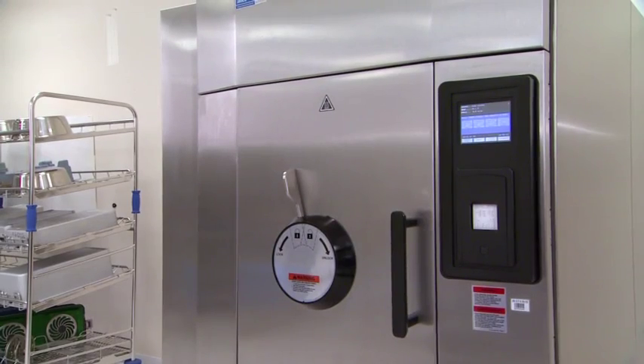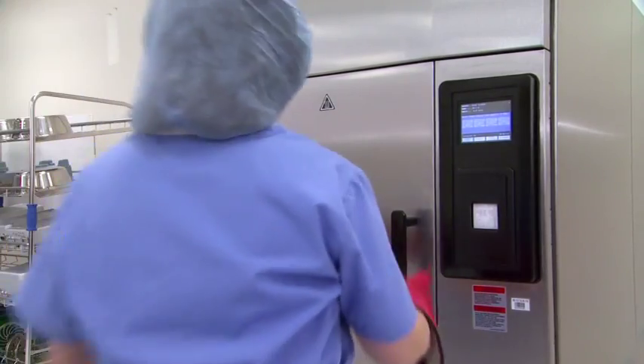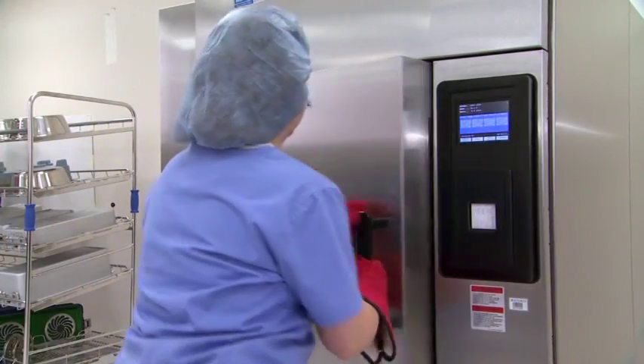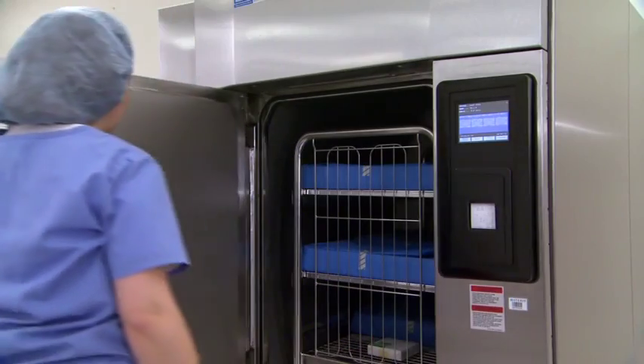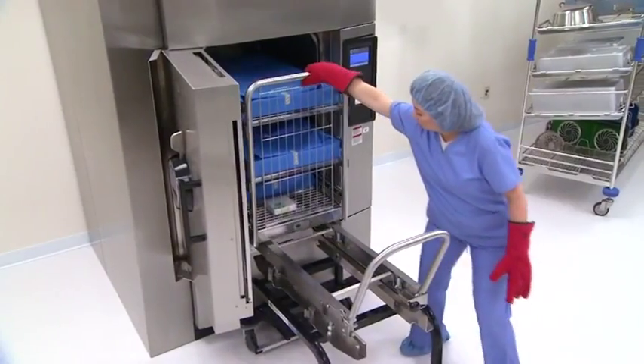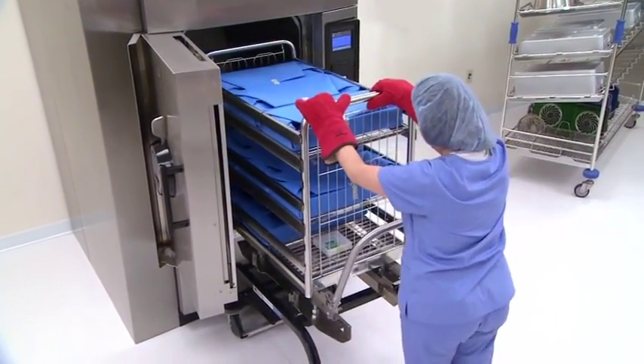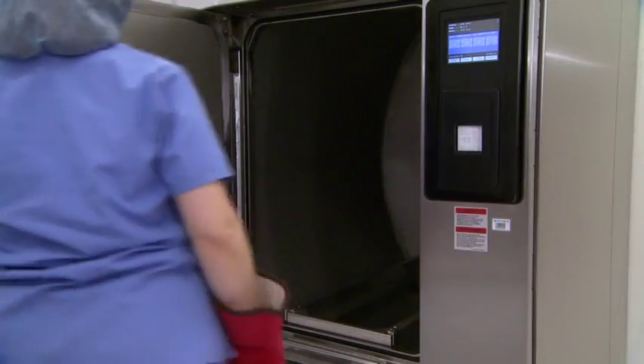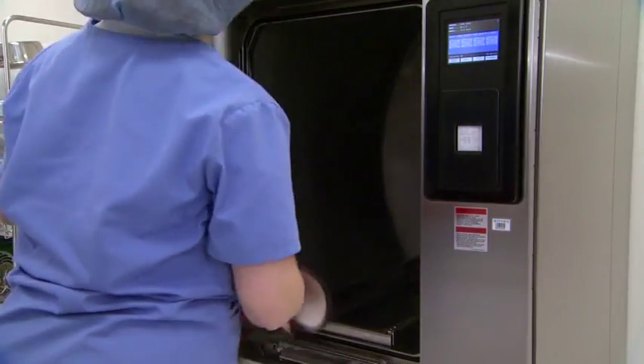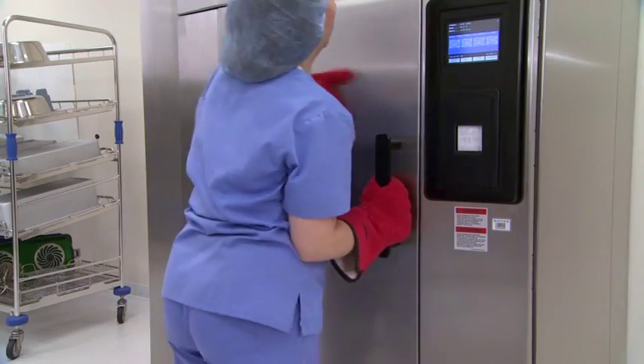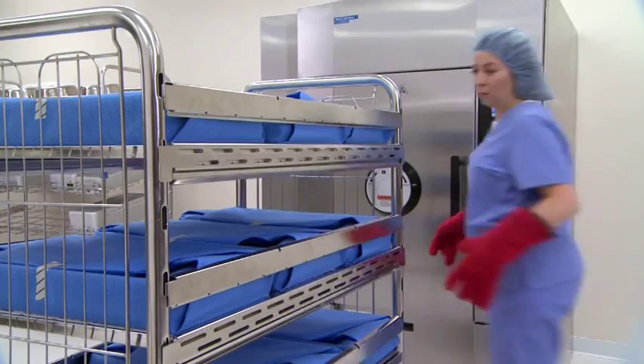At the end of a cycle, when the end of cycle tone sounds, open the chamber door. Wear clean gloves and use clean towels as pot holders to carefully remove the load and avoid unnecessary handling. After removing the load from the chamber, close the chamber door and keep it closed to minimize utility consumption.